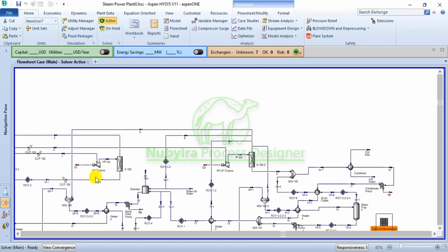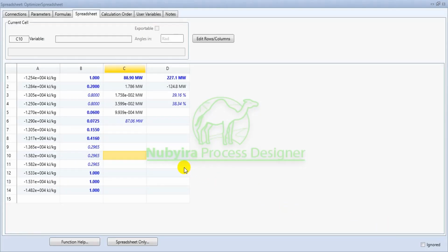we use the steam enthalpy of the system, because the calculation of the power produced is going to be based on the efficiency of this turbine and the enthalpy of the steam. At high pressure temperature, the enthalpy is going to be very high. High superheating temperature, the enthalpy is going to be very high. And if the pressure gradient is low, then the enthalpy of the moist steam, the exhaust steam that is coming, will be very low. So the difference in the enthalpy will be used to calculate the specific power produced from the turbine, you understand. And it's going to be based on the mass flow rate of the steam. So it's going to be power produced per kilogram of mass produced in the steam that is supplied from the boiler.